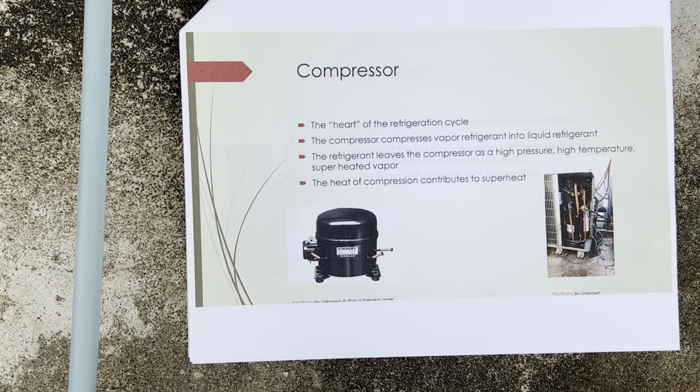So where does this refrigerant gain all that heat? Because it comes in to the compressor at a lot lower temperature. So where does it gain all that heat? Well, the main place it gains that heat is the heat of compression. Once you go to compress vapors, just the heat of compression will add heat into that refrigerant, and the fact that we're pushing it to a higher pressure. Of course, temperature and pressure are related, so the higher the pressure is, the higher the temperature is going to be. So that's why that refrigerant can get so hot.